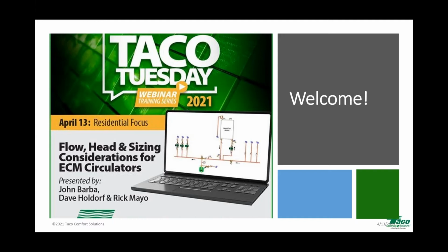We're psyched. We've got a pretty cool presentation for you today called Flow, Head, and Sizing Considerations for ECM Circulators. And this one's kind of near and dear to all of our hearts here at Taco, and it's important, I think, for everyone to really fully understand, because even though ECM variable speed circulators have been with us for a while, people still think they're magic. People still don't understand that we're talking about system curves, we're talking about pump curves, we're talking about control curves. The fundamentals of circulator selection still apply, even though these things can in fact vary their speed or have different performance ranges beyond just a normal fixed speed or even a 3-speed circulator. They can do interesting things, but they don't size themselves. They're not magic. They're not anything like that.